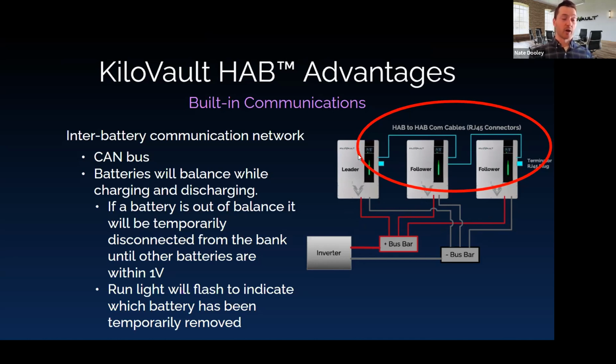When we talk about balancing, we're not really concerned about 1 volt or a few tenths of a volt difference, and you'll hopefully see that resolve itself over time. They're probably never going to be exactly the same voltage, and that's okay. What will happen is as they charge and discharge, the voltages will balance out so that they're all roughly within 1 volt or so of each other. And as long as they are, that's what we care about.